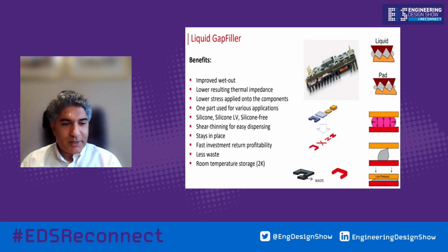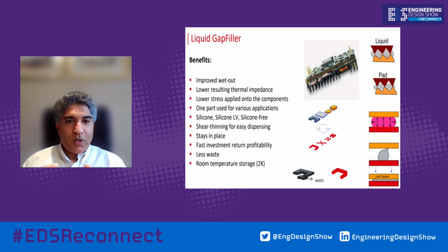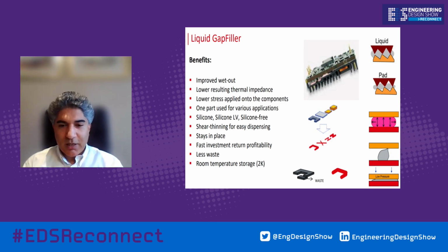Okay, so paste. The Bergquist liquid pastes are cure in place, room temperature cure, and fill in nooks and crannies, so you haven't got a concern about it flowing out. Depending on the material, it could actually stay in place, and a cure in place will have a good bond. It's not a permanent bond, but it'll stick to the substrates. You save money, whereas with the gap pad you're paying for the waste.